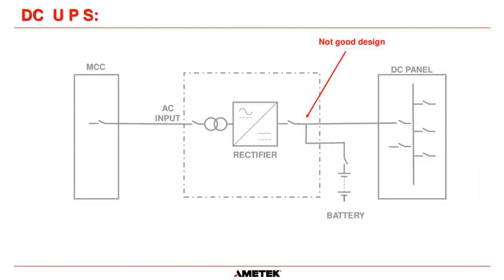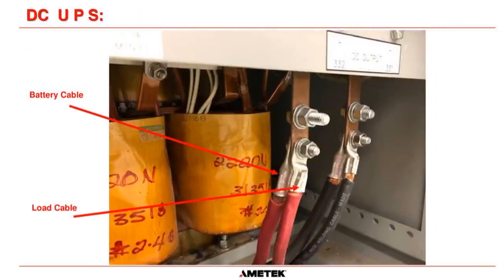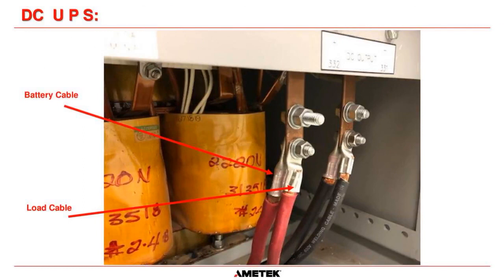Now, here are some systems that are poor design. Obviously, I've worked in the field for 20 years, and I've seen about as many of the poor designs as you can imagine. One of the most common things is when somebody connects the battery cables onto the output cables of the charger. Now, it's not easy to see on this drawing here, so it just so happens I have a picture. And this shows you here. So this is the positive bus bar here, and this is the negative bus bar here. Now, they've connected the load cable on the front lug and they've connected the battery cable on the back lug.